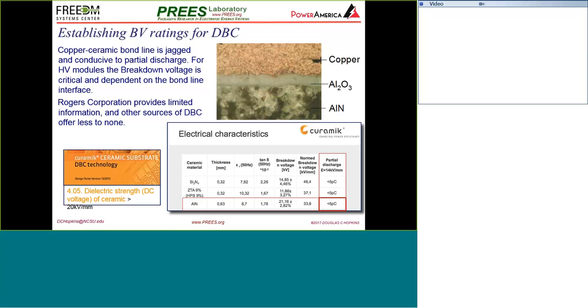So all that said, I am posting here from Rogers Corporation. The fact is that they actually did PD testing, partial discharge testing, and established that they can go at 14 kV per millimeter at less than 5 picocoulombs. At 5 picocoulombs, you're actually counting the number of electrons flowing through, which you can then use to say this is the voltage withstand I can have for my module. So under this, the 25 mil or 635 micron thick ALN ceramic we're using should be able to withstand our 10 kV design.